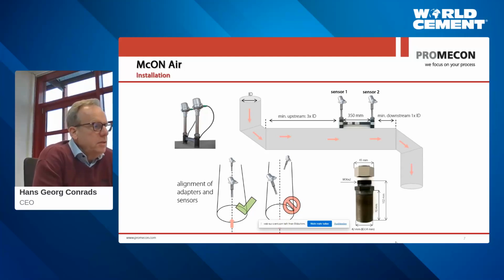A few things are important. One thing is that the sensors have a known distance. In this case, we're talking 350 millimeters. Another thing that, of course, is important is that the sensors are aligned. We don't like twisted sensors, because then whatever flows by sensor 1 does not flow by sensor 2 maybe. And if they are twisted such that they are not parallel, you will also have the danger of a change in distance of the sensor. The average distance of the sensor changes, you will induce a linear error. In order to prevent that, we have these mounting brackets. The mounting brackets have a fixed distance, and the mounting brackets are parallel, so that the sensor is looking down parallel. The other thing you should mention is that you have enough ID upstream distance.